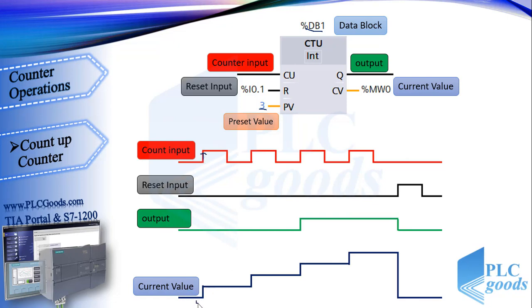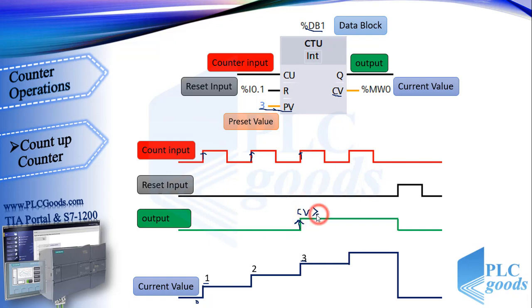Let's see how outputs change with this diagram. When we have a positive signal edge at the counter input, the count value CV will increment by 1. With another positive signal edge, the counter value changes from 1 to 2. Finally, with the next pulse, the counter value reaches 3, which is equal to its preset value. At this moment the output changes from 0 to 1. For this counter, when the counter value is equal to or greater than the preset value, the output will be on.